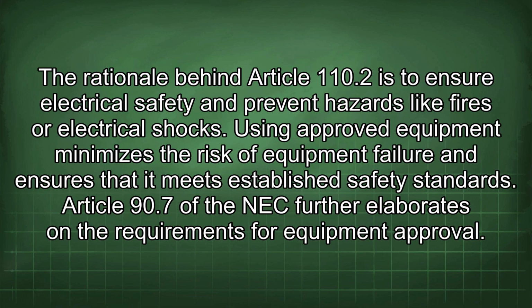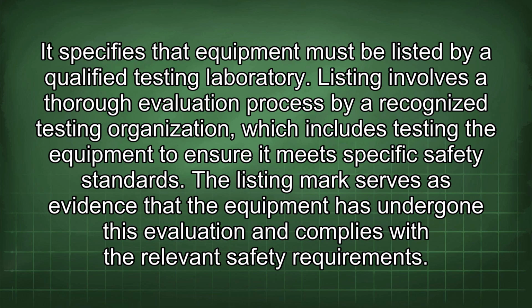The rationale behind Article 110.2 is to ensure electrical safety and prevent hazards like fires or electrical shocks. Using approved equipment minimizes the risk of equipment failure and ensures that it meets established safety standards. Article 90.7 of the NEC further elaborates on the requirements for equipment approval. It specifies that equipment must be listed by a qualified testing laboratory.